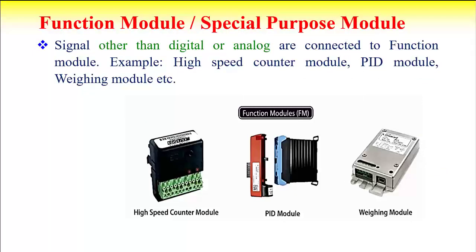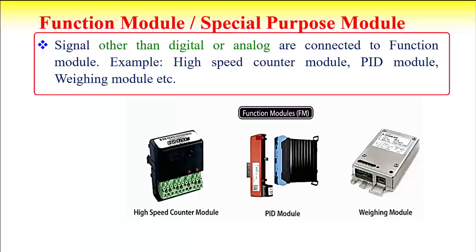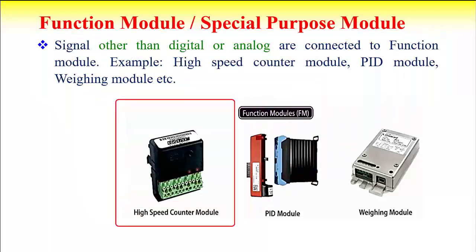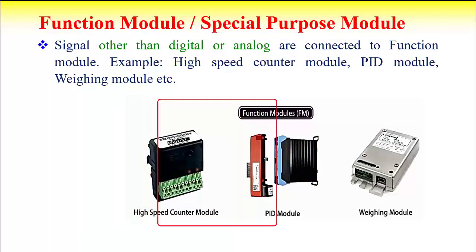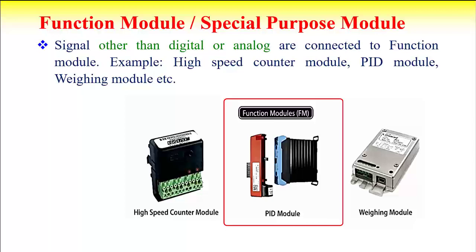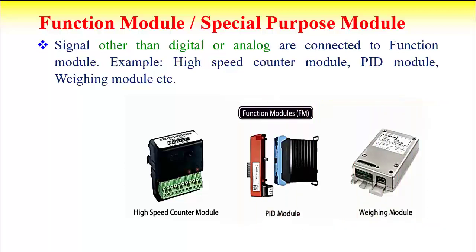Function modules, also called special purpose modules, are used when signals other than standard digital or analog are connected. Examples include the high-speed counter module — used to count high-frequency signals — the PID module used for process control systems, weighing modules, etc. These special purpose modules are used for functions that cannot normally be achieved using standard digital or analog PLC modules.